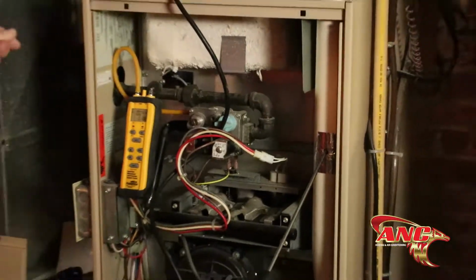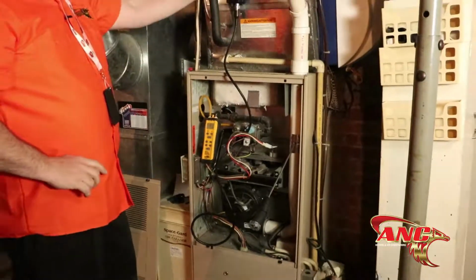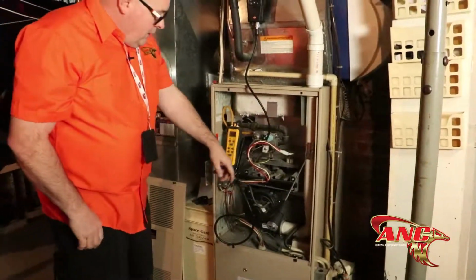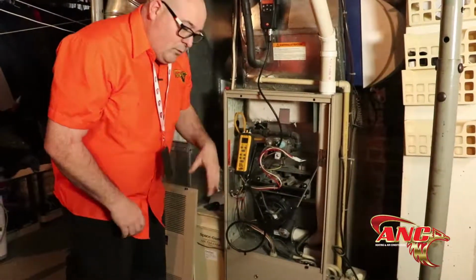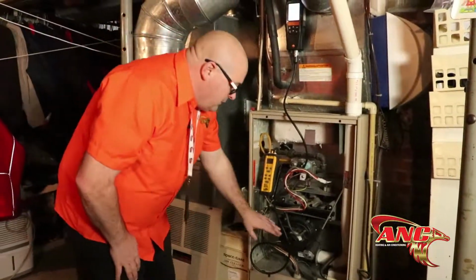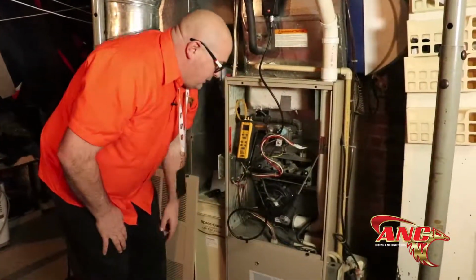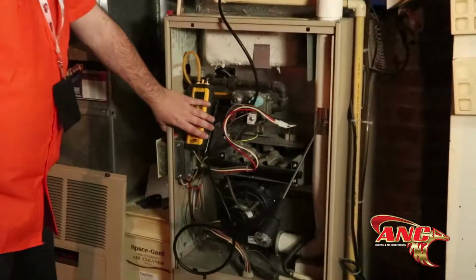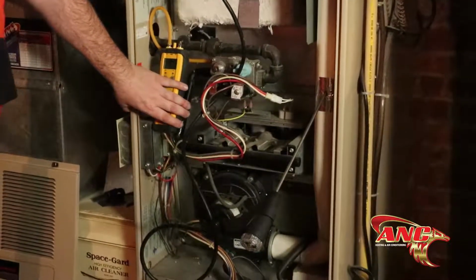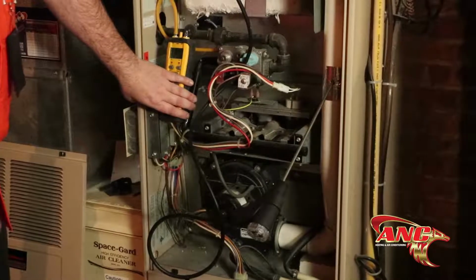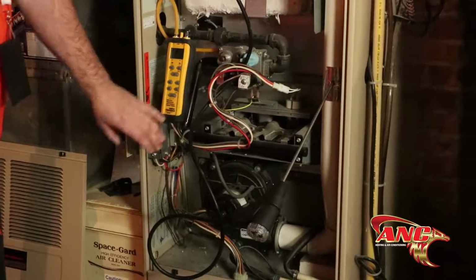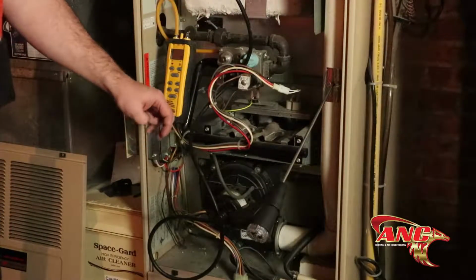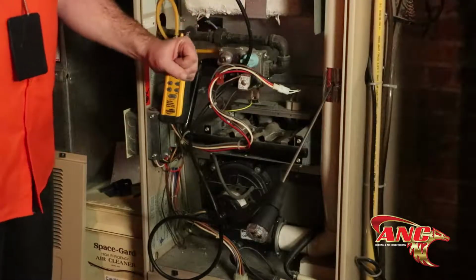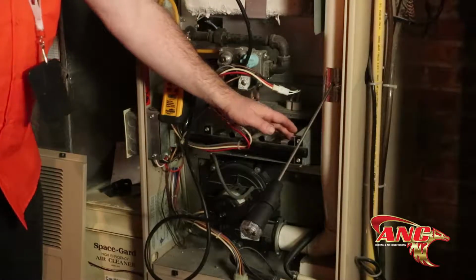Now, when I start this furnace up, we're going to look for a couple of things besides the numbers. I want to make sure, one, we're going to listen. We're going to listen for noise. I've already blown these drains out clean. We're going to look for gas pressure. I want to see it around 3.5, 3.2 to 3.5. I may make an adjustment on this. Also, when the flames start up, I don't want to see the flames come out. We call that a flame rollout.